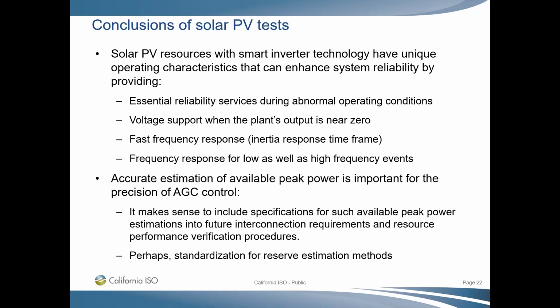And we had another question, just a point of clarification. They wanted to confirm, were you saying previously that solar PV is able to absorb MVARs? Yes. The solar PV plant can operate similar to a conventional unit, either a hydro unit or a gas unit. You can operate at a lagging power factor, which means you're producing reactive power onto the grid, or at a leading power factor, consuming reactive power from the grid. The newer solar plants can provide reactive support to the grid, and they can also consume reactive power from the grid.